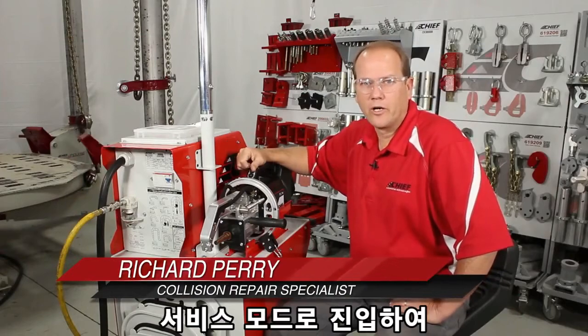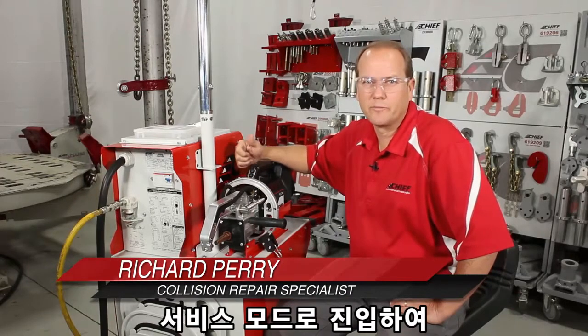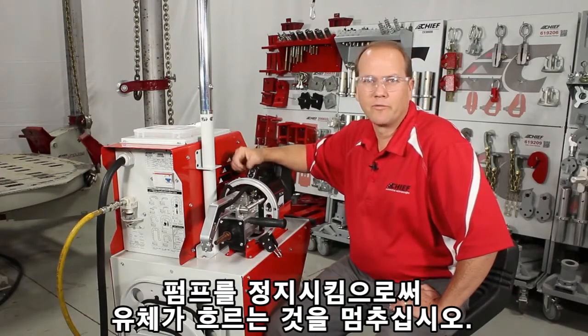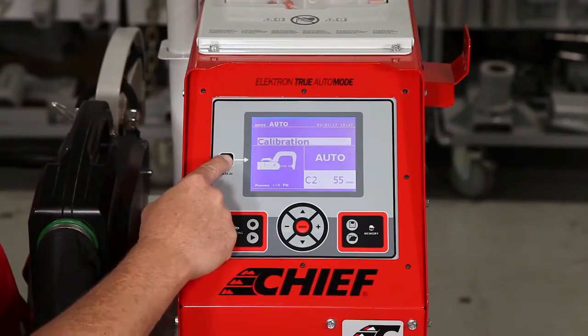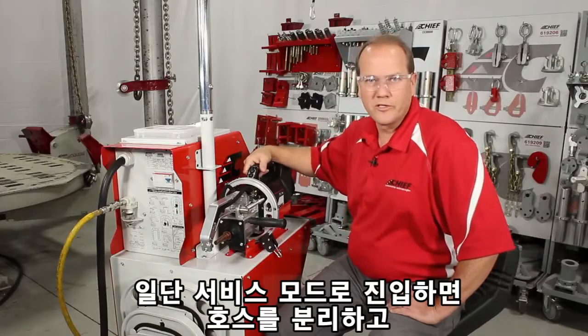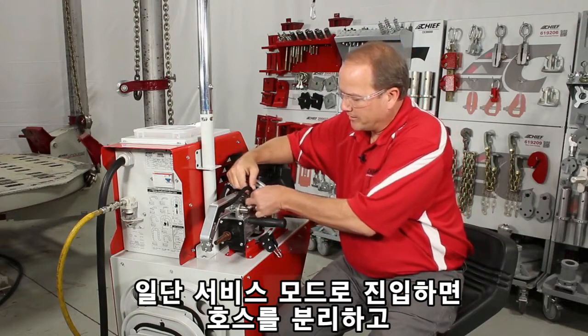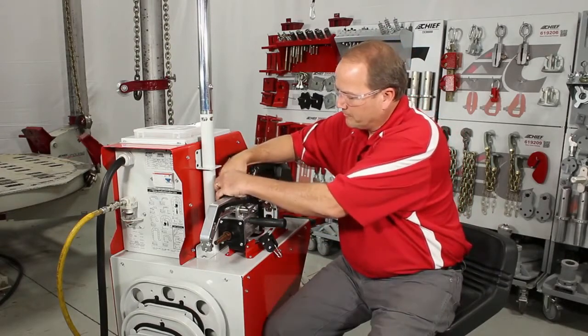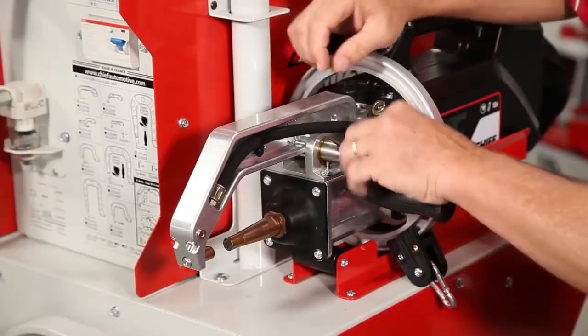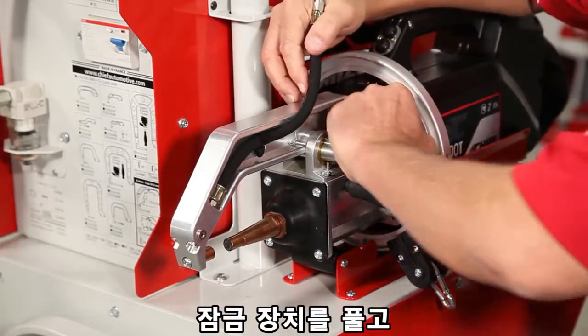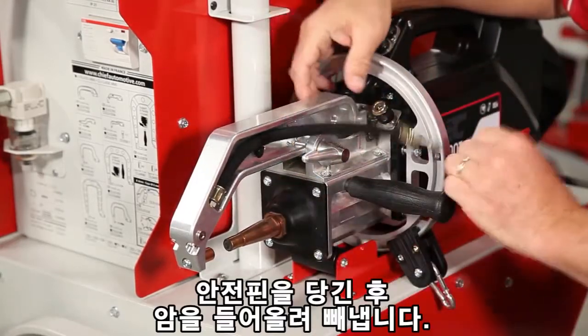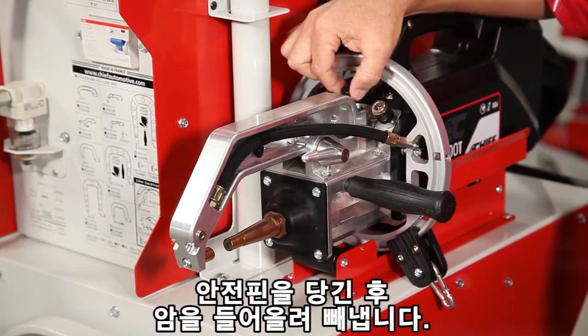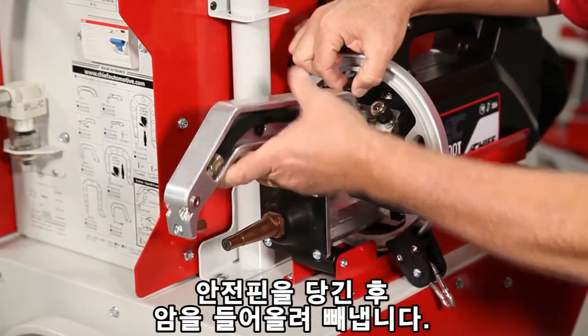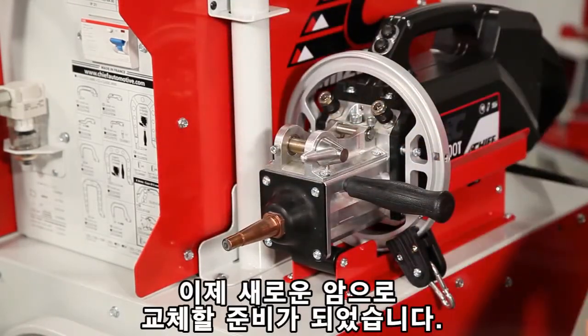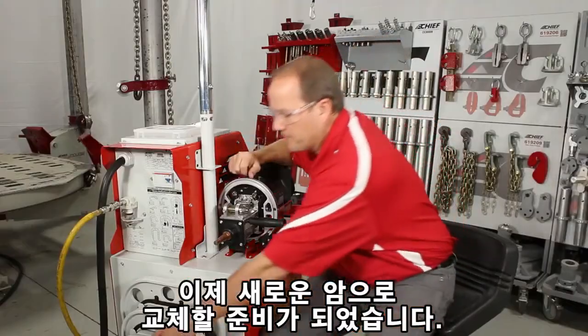Before changing out the arms, we must first put this in the service mode to stop the pump and the fluid from flowing. Once in service mode, then we can disconnect the hoses, release the lock arm, and release the safety latch. Flip the arm up and remove the arm, and we're ready to replace it with the new arm.